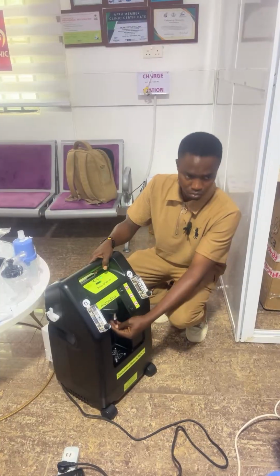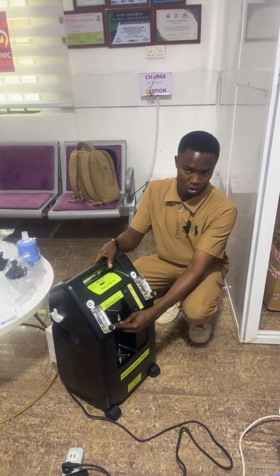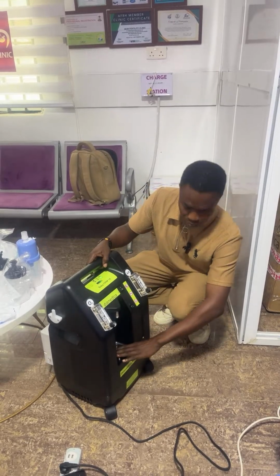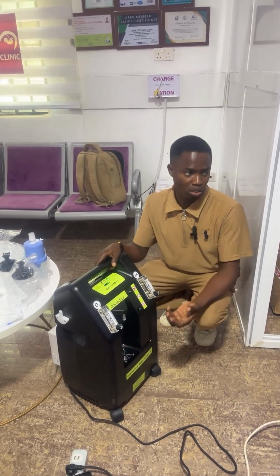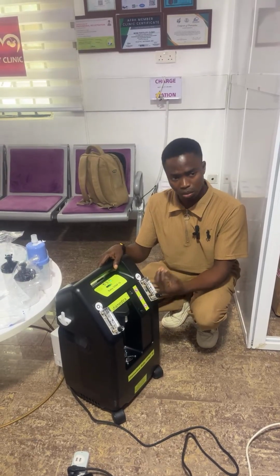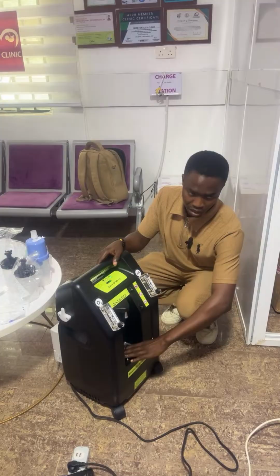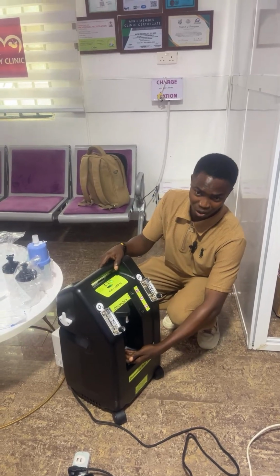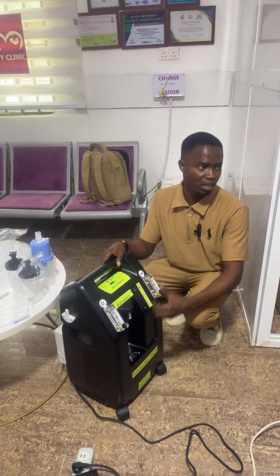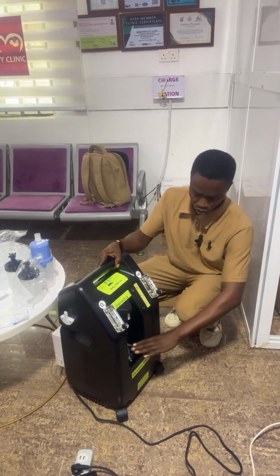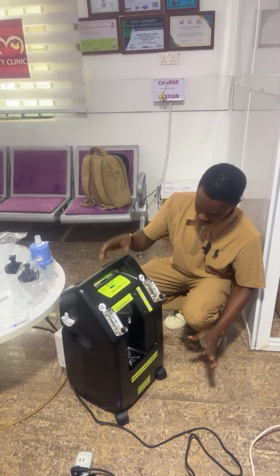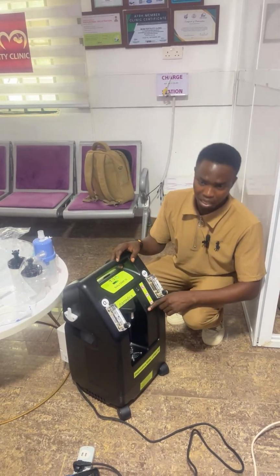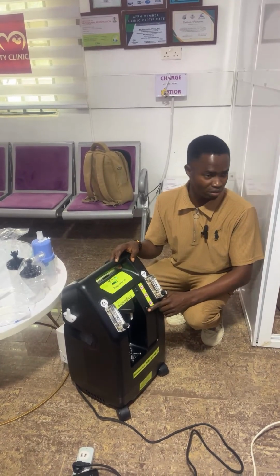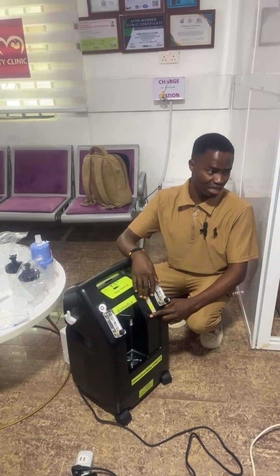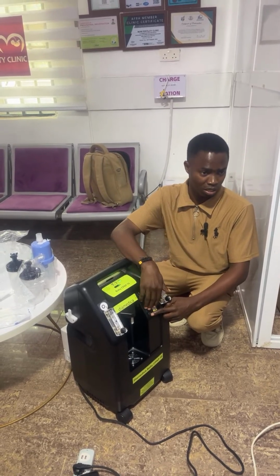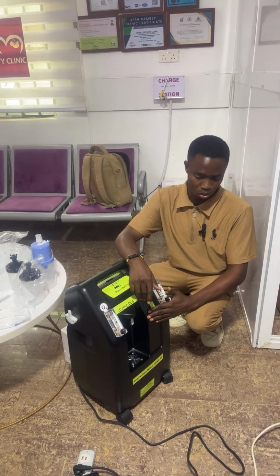This is the outlet where the gas mixture comes out from. This is where your humidifier will be, and this part should not be covered. We all know oxygen is cold, and cold oxygen is not good for the newborn. So this helps to warm it. It's not very hot. If you put your hand, you won't feel it hot, but you know that it's not delivering cold oxygen to the patient. So it must not be covered. It must be left open like this. This part here, some people can tamper with it, but it's not good to touch it. If you touch it, don't do anything. It's like a safety device, like a breaker inside the machine. So there's no need touching it or putting it on.